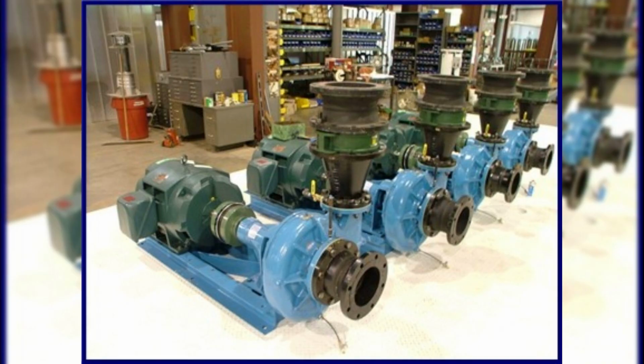First, in-line circulating pumps. These are designed for a horizontal mount with a vertical split case. They come with a cast iron body, an alloy steel shaft, and oil-lubricated bronze bearings with a mechanical seal for durability. The impeller is enclosed and dynamically balanced for smooth operation. The motors are built to be non-overloading, drip-proof, and equipped with thermal overload protection. For the connection, they use a flexible, self-aligning coupling that helps reduce wear and makes service easier.